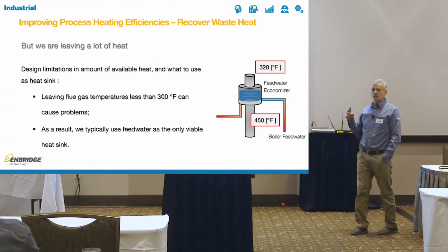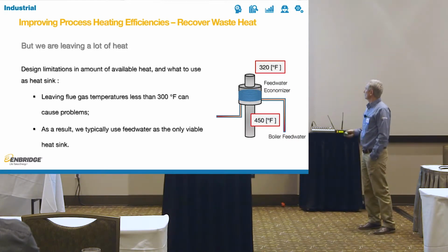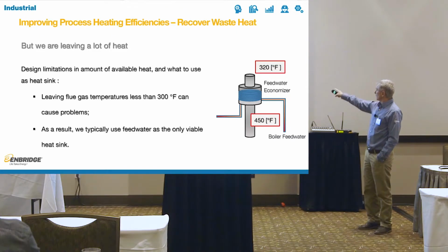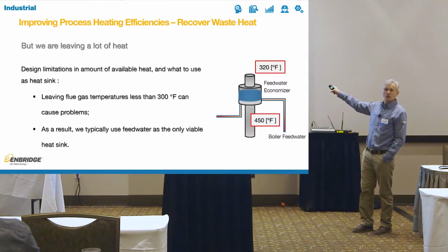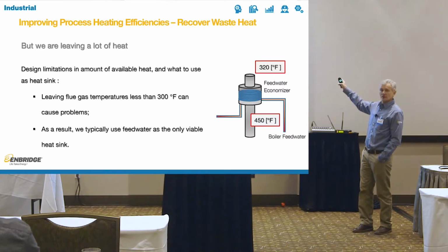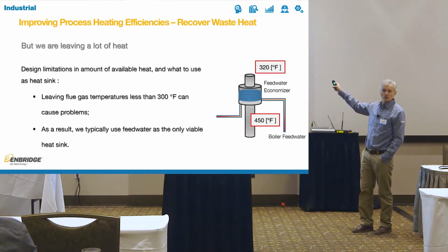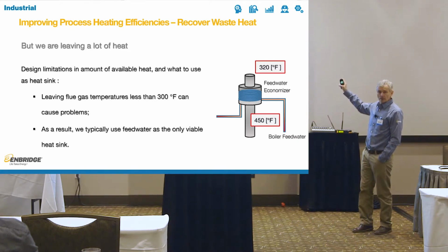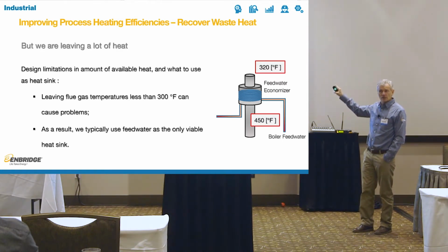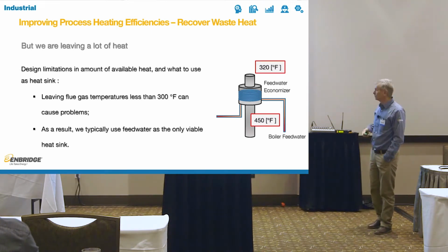The problem with the Feedwater Economizer is that you're leaving a lot of heat. For example, if the flue gas temperature is 450 degrees F out of your boiler and into the economizer, it's going to leave at about 320 degrees F, which is still pretty warm exhaust. A Feedwater Economizer is designed in such a way that you cannot get flue gas temperature down below 300 degrees F by much, because then you're in danger of condensing, and that's going to eat your Feedwater Economizer, which will not be good for your payback periods.